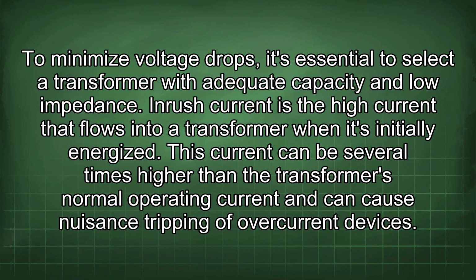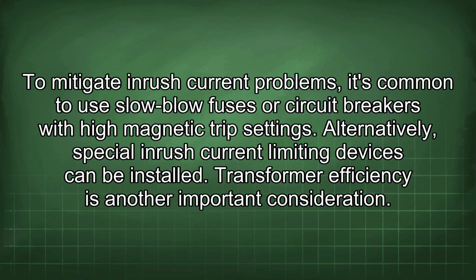Inrush current is the high current that flows into a transformer when it's initially energized. This current can be several times higher than the transformer's normal operating current and can cause nuisance tripping of overcurrent devices. To mitigate inrush current problems, it's common to use slow-blow fuses or circuit breakers with high magnetic trip settings. Alternatively, special inrush current limiting devices can be installed. Transformer efficiency is another important consideration.